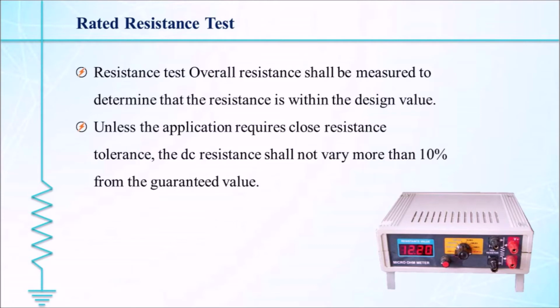First test is the rated resistance test. In this test, using a digital ohm meter, the DC resistance value is tested and recorded at ambient temperature and corrected to the required resistance value. According to IEEE rules, the acceptance tolerance in that value is plus or minus 10%.